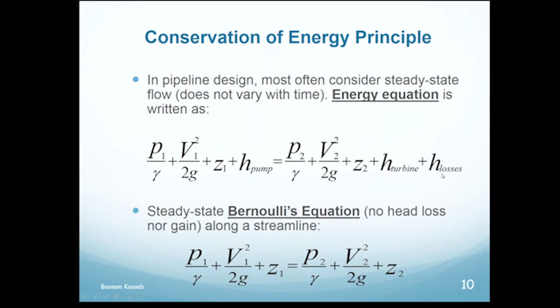And this is for you to come back to later if you want to understand the definition of each term: pressure head, elevation head, velocity head. Now, piezometric head means the pressure plus the elevation head. That's what you call piezometric. People who work in this field, especially operators and maintenance technicians, see that word often, piezometric head, or mostly they call it hydraulic grade line, or HGL. So that term is important to know, and it does not include the velocity. And it's not only the pressure, it's the pressure plus elevation of the pipe.